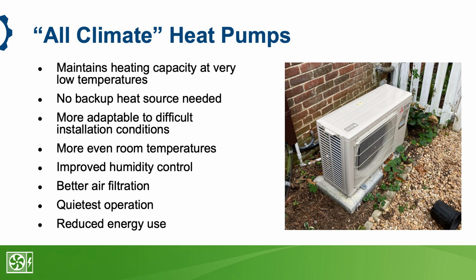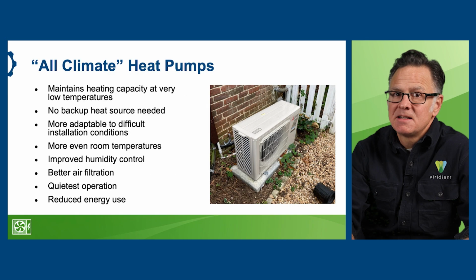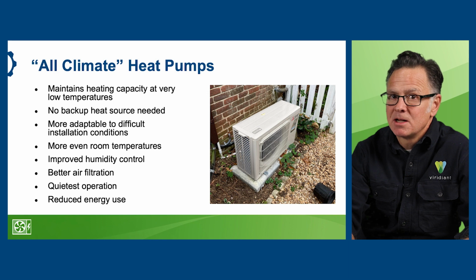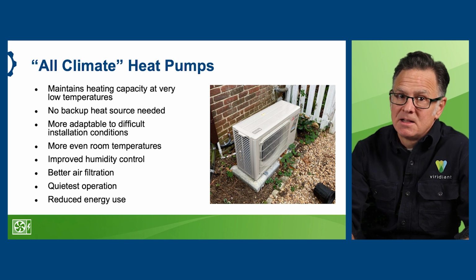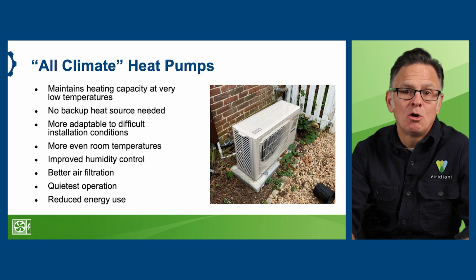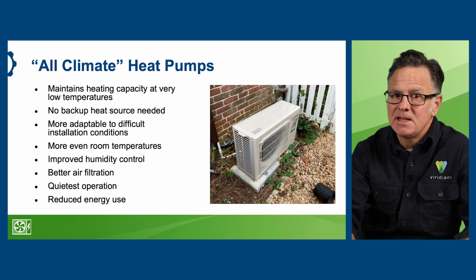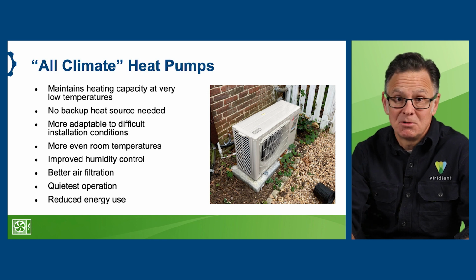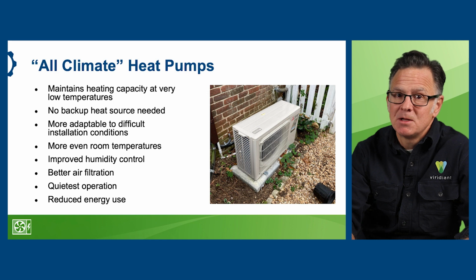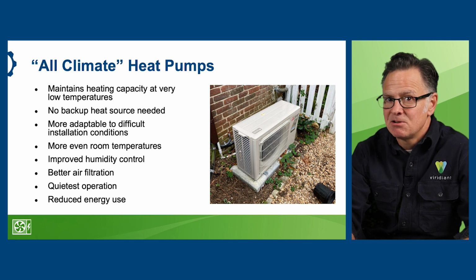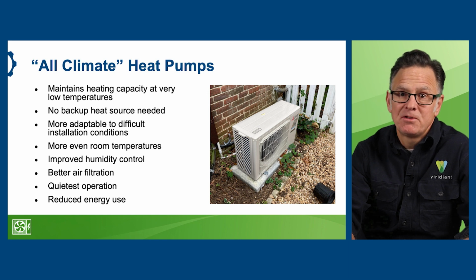Inverter technology, one of the keys to super high performance heat pumps, is often regarded as new, but actually it's been around since the 1980s. Today, more and more inverter equipment options are hitting the market. They are highly efficient and amazingly quiet. The highest performing inverter heat pumps are often called cold climate systems. They can maintain full heating capacity even when outside temperatures are less than 0 degrees Fahrenheit. That means, depending on the local climate, auxiliary heat does not need to be installed for these systems. Also, these models generally require less power, which allows for lower amperage breakers and easier integration into existing electric panels. In retrofit situations where you might want a heat pump to replace a gas furnace or boiler, access to sufficient electrical power sometimes is an issue.